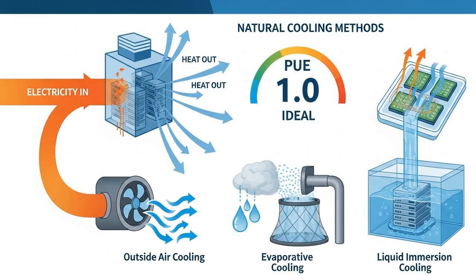We measure the efficiency of this process using a metric called power usage effectiveness, or PUE. An ideal PUE is 1.0, meaning every single watt of power goes into computing. Of course, that's just a theoretical dream. In reality, a really good land-based data center might achieve a PUE of around 1.1, but the global average is much higher, showing there's a lot of room for improvement.